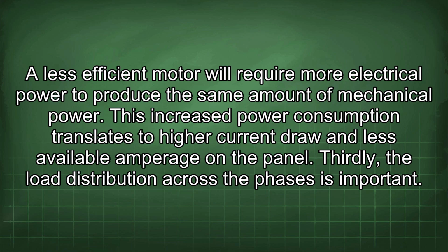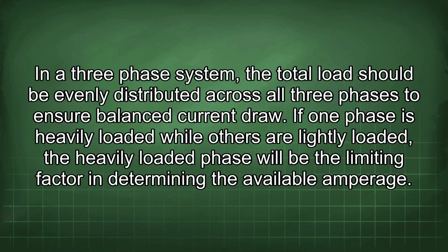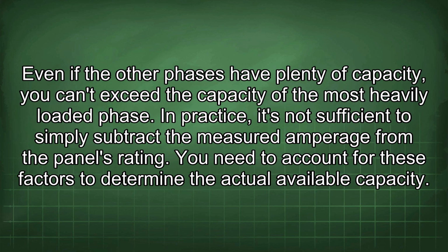Thirdly, the load distribution across the phases is important. In a three-phase system, the total load should be evenly distributed across all three phases to ensure balanced current draw. If one phase is heavily loaded while others are lightly loaded, the heavily loaded phase will be the limiting factor in determining the available amperage. Even if the other phases have plenty of capacity, you can't exceed the capacity of the most heavily loaded phase.